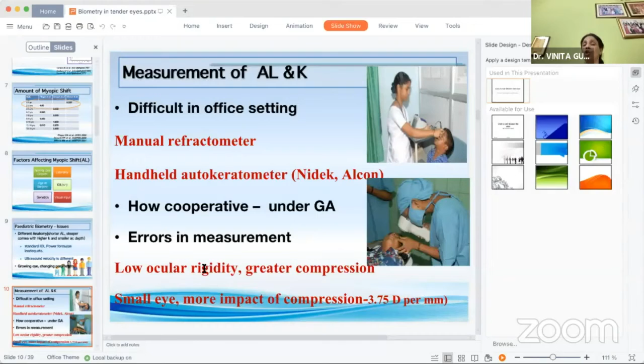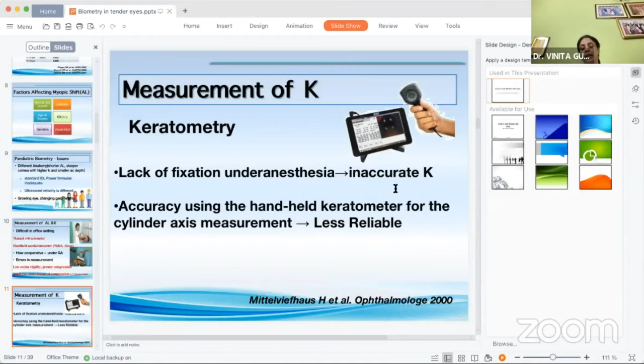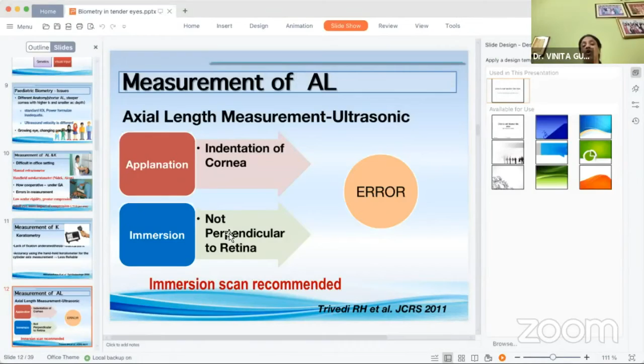Obviously, their accuracy is less as compared to the stationary keratometers, the automatic keratometers, which are kept in the OPDs. And secondly, there is the lack of fixation under anesthesia, leading to inaccurate K readings. As regards measurement of the axial length in children, again, we are more commonly using ultrasonic methods, under general anesthesia. So whatever modality you are using, whether immersion or applanation, we are not exactly perpendicular to the retina. Although if you have to use one, immersion scan is the recommended scan. The best is to measure in an aphakic mode in these cases and use the CAF method to do the IOL power calculations.